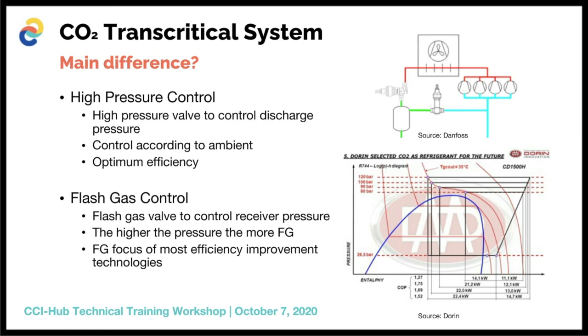So this is where the two main control differences come in, between the high pressure and the flash gas control valve. The benefit of this is you can basically determine where you are running your discharge pressure, because you do have a high pressure valve controlling your optimum pressure. This is also critical when it comes to the operation of the system, where depending on what your gas cooler outlet is, which is determined by the ambient conditions, your controller will determine the optimum place for your system to operate to have the most efficient operation.